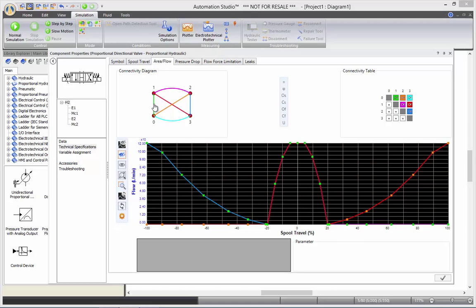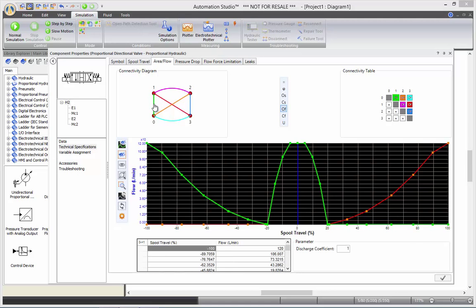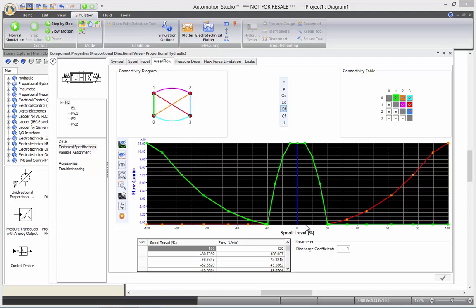If I select the port 0 to port 1, the flow on spool travel relation is illustrated here. I have a 12 liter by minute flow if my directional valve is completely to the end. Or I have an open center, so from about minus 10 to 10 percent travel, I also have the maximum flow of about 12 liter by minute.